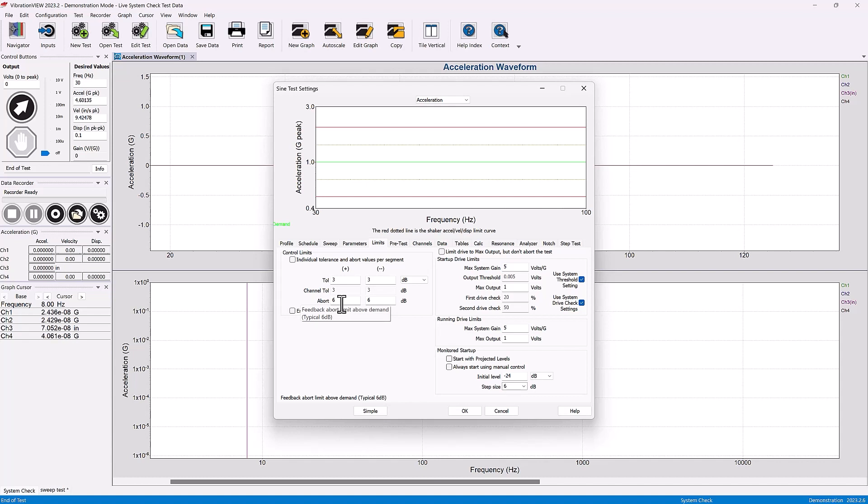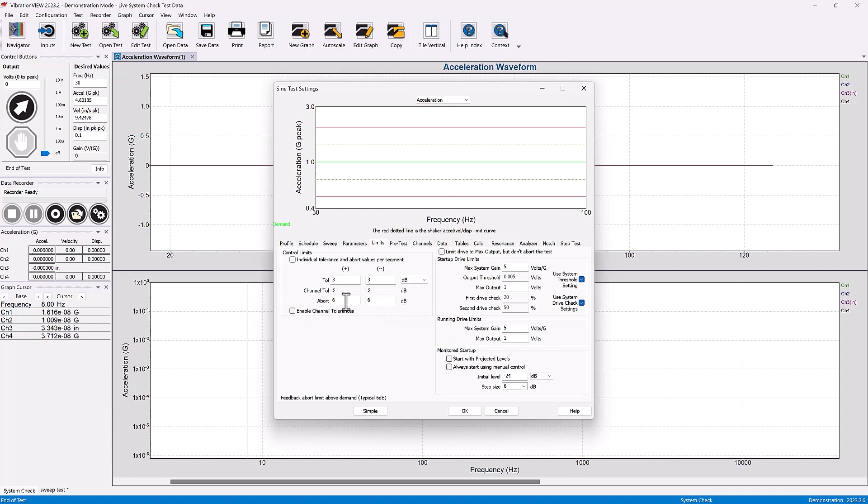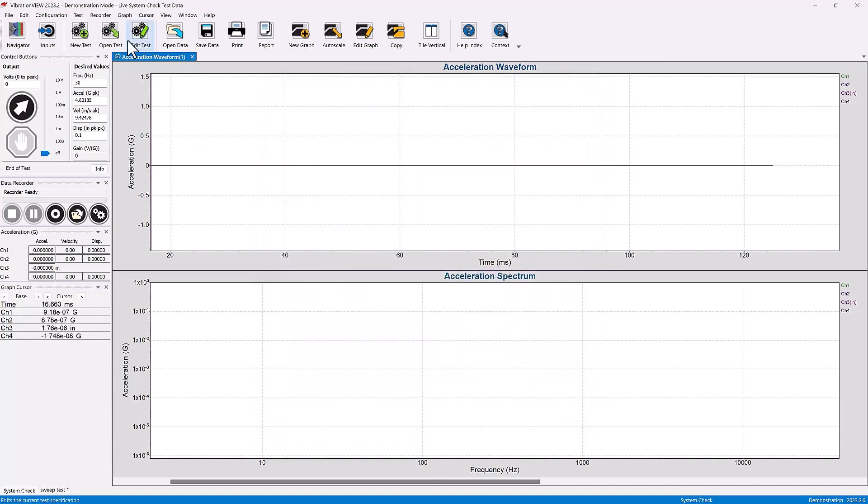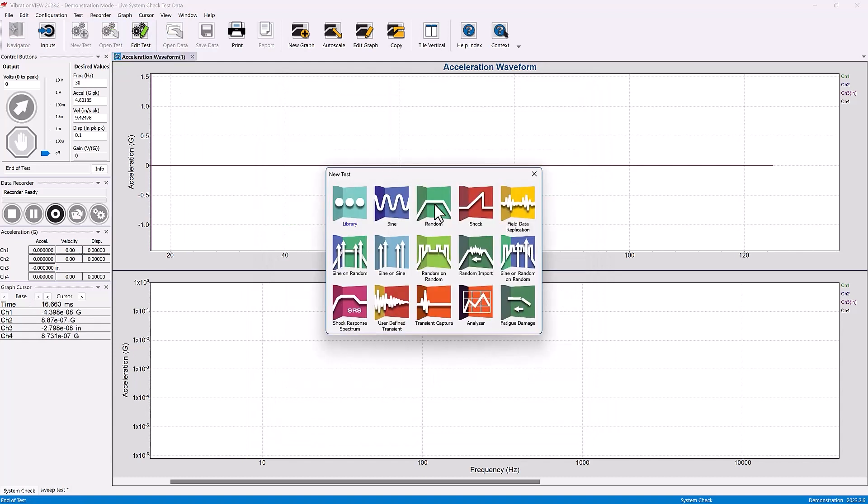There's an abort limit that we're going to set and that's generally 6dB. In the sine test that's found under the limits tab. If we open up a random test...